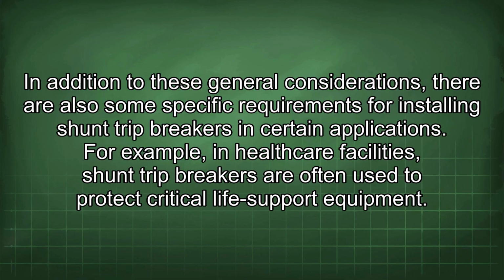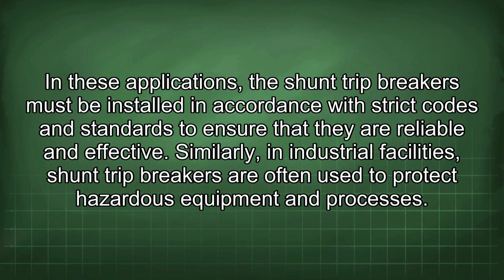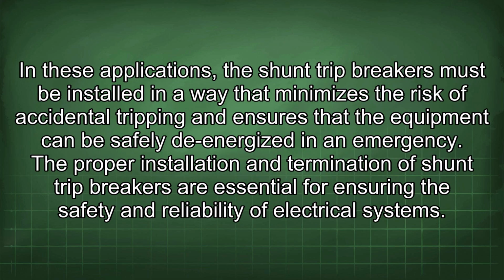In addition to these general considerations, there are also some specific requirements for installing shunt trip breakers in certain applications. For example, in healthcare facilities, shunt trip breakers are often used to protect critical life support equipment. In these applications, the shunt trip breakers must be installed in accordance with strict codes and standards to ensure that they are reliable and effective. Similarly, in industrial facilities, shunt trip breakers are often used to protect hazardous equipment and processes. In these applications, the shunt trip breakers must be installed in a way that minimizes the risk of accidental tripping and ensures that the equipment can be safely de-energized in an emergency.